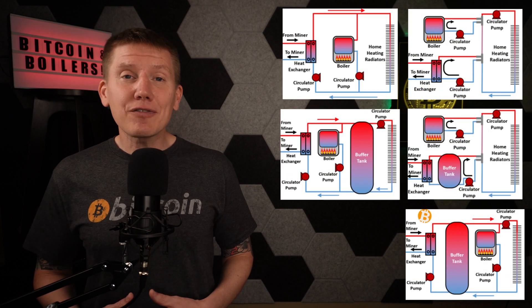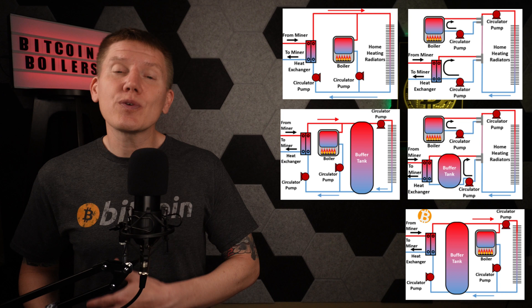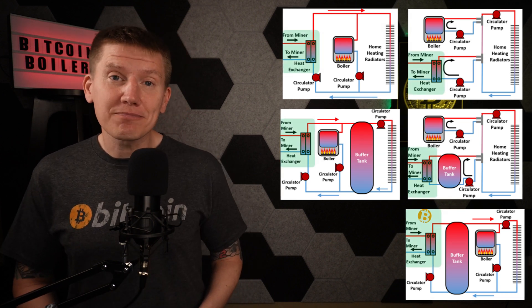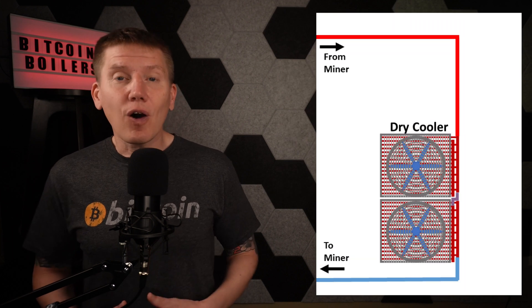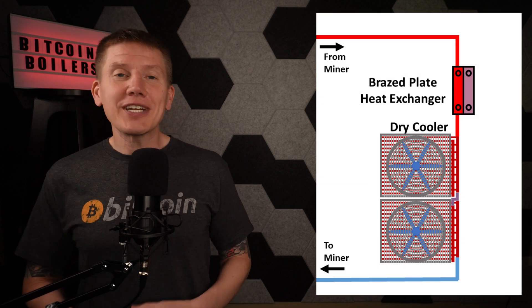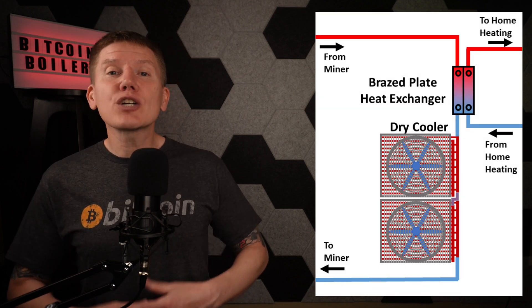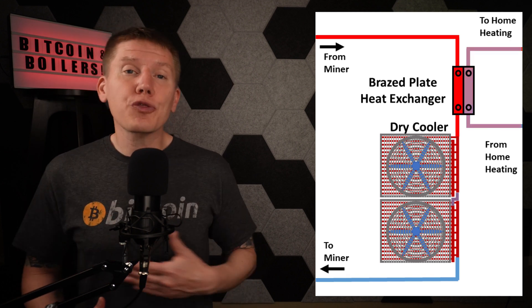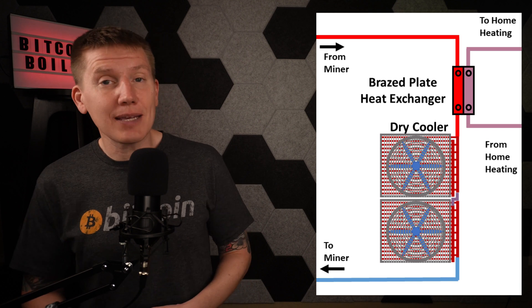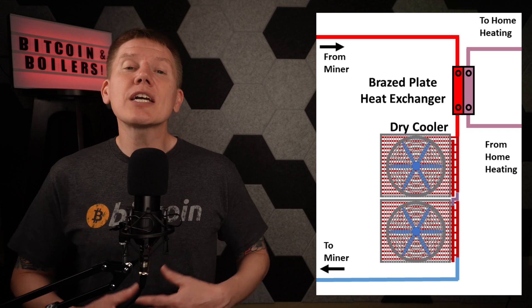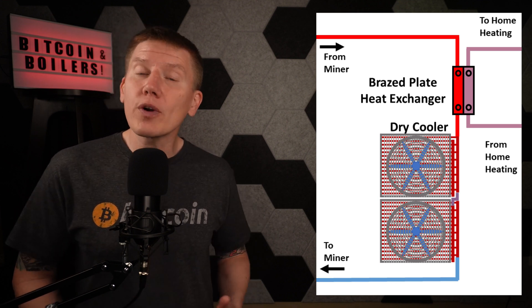This is where hydronic heating setups make things really easy. In every one of these configurations, heat is transferred between the Bitcoin cooling loop and the home heating loop using a brazed plate heat exchanger. On the miner cooling loop side, all that is needed is to place this brazed plate heat exchanger before the dry cooler. When heat is needed by the home heating system, the heat exchanger will pull heat from the Bitcoin miner loop. When heat is not needed, the fluid will pass through the heat exchanger staying at the same temperature. Either way, the Bitcoin cooling fluid will continue to the dry cooler and be completely cooled down before it returns to the miners.